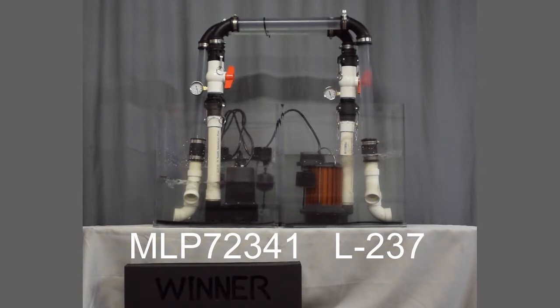I'll point out that they're both dialed into 4 PSI in the pressure gauges. That represents an average lift installation of 10 feet.